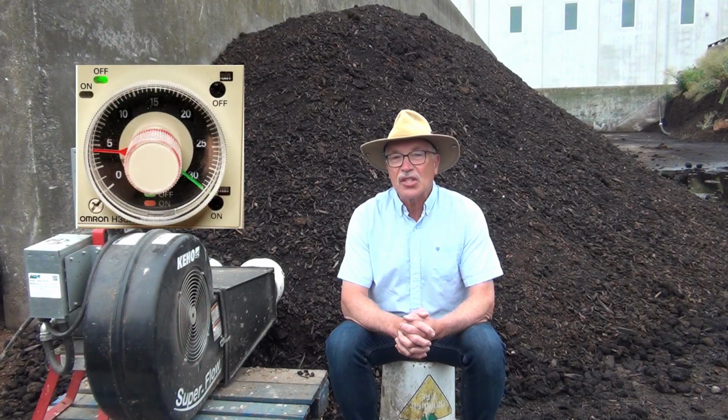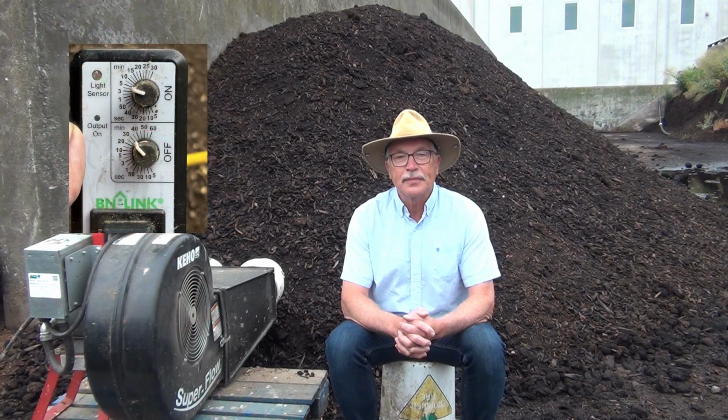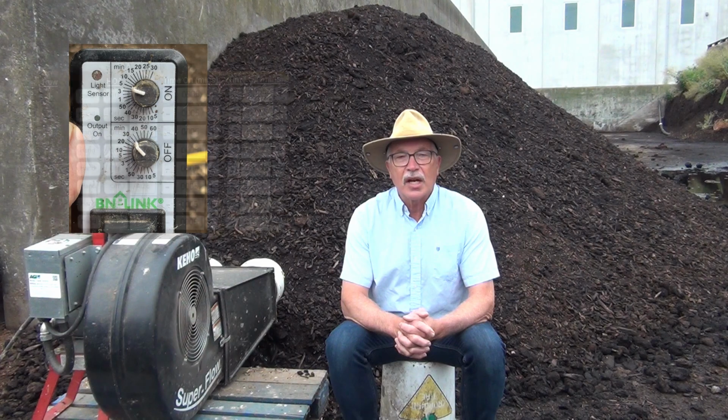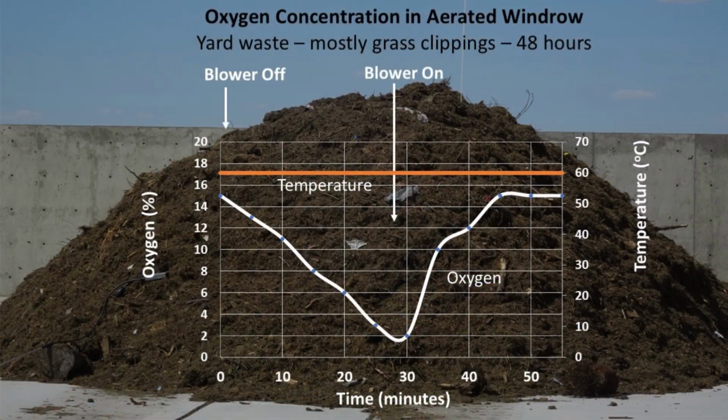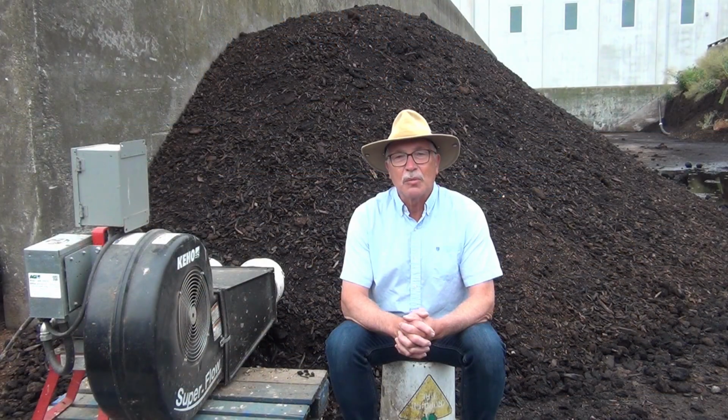For 20 years, I've focused on two primary control strategies. The first is using a timer, whether it's a physical timer or a PLC. I normally recommend starting with the blower operating every 30 minutes. However, with some high-energy materials, we need to operate the blower every 15 minutes.